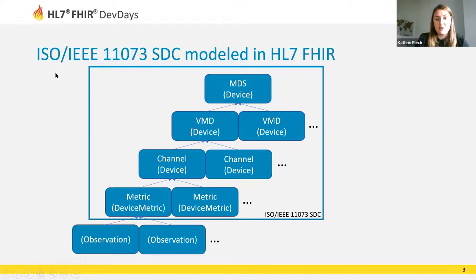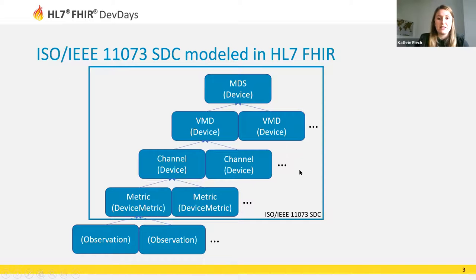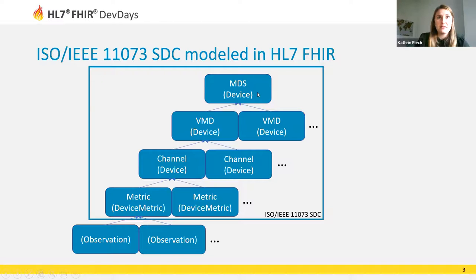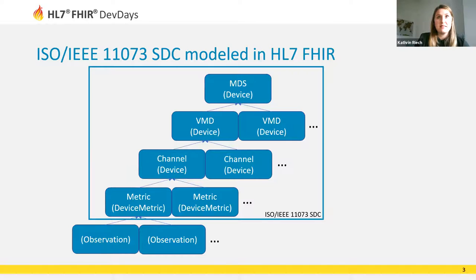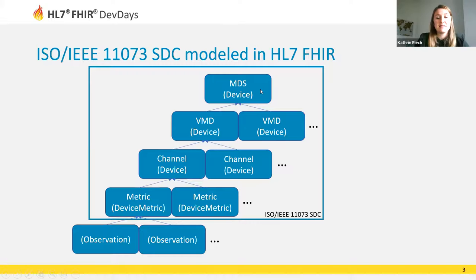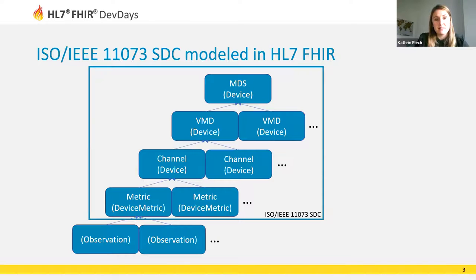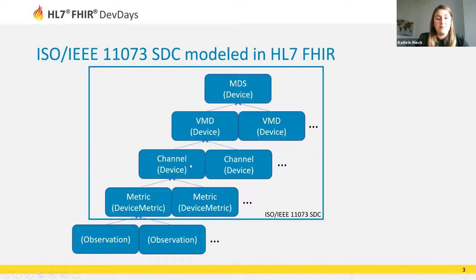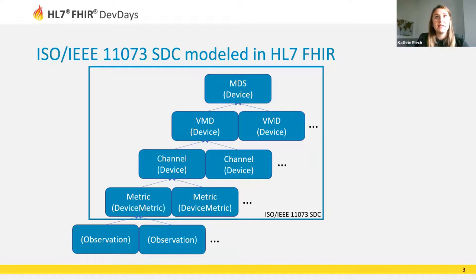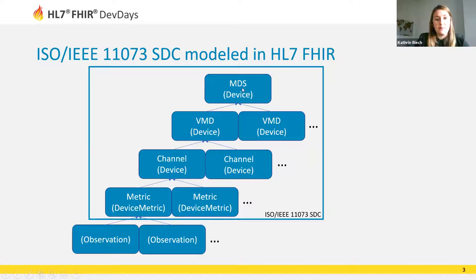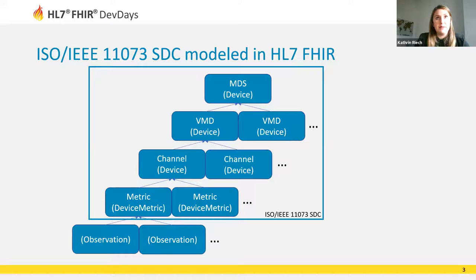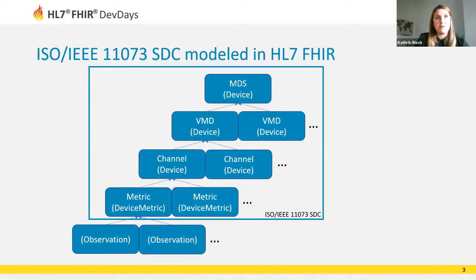So in 11073 SDC, the device information is organized hierarchically in four layers. The uppermost level is the object-oriented abstraction of the point of care device, the medical device system, followed by the virtual medical device on the next level which represents the abstraction of a medical subsystem. The channel allows us to group, to make logical groupings of metrics for hierarchical information organization. These three levels are all modeled as Device resources in FHIR.